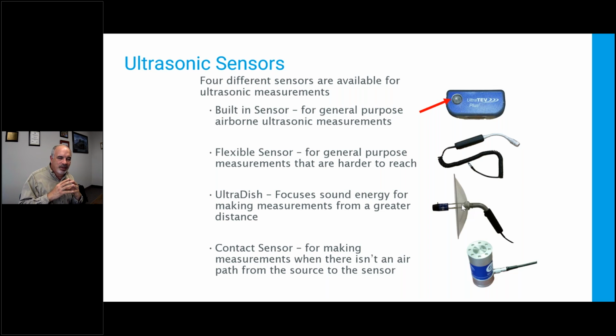We've had situations where, okay, I've gotten some PD. I don't want to open that cabinet door. I've got some indication of my PD because that cabinet door's got compromised insulation. I can use the dish. I can stand back, safe distance, have someone else open the door with an arc flash suit on, and find that PD. We've been very successful with that.